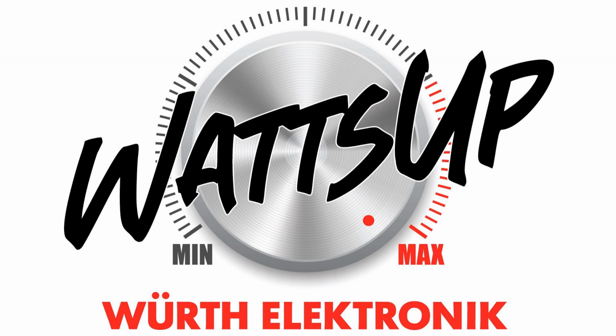So here are the transformer design parameters. We have an input voltage range of 85 to 265 VAC, output 1 of 15 volts at 1 amp, output 2 and output 3 at 15 volts at 50 milliamps. That's after regulation. We have an auxiliary winding, 18 volts at 20 milliamps. Frequency is about 70 to 80 kilohertz. And for this design, we will be meeting UL 60950 with reinforced insulation. And this transformer runs in DCM mode.